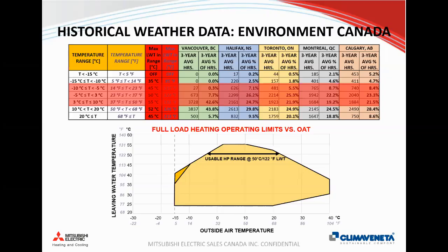So for example, if we look at a 50 degrees Celsius supply, if we look at the operating envelope, we can basically only manage that temperature as low as -5 and as high as about 22 degrees. So again, on the y-axis here, we have leaving water temperature that the air-to-water heat pump can produce according to outside air temperature. So for example, 55 degrees Celsius is the maximum supply water temperature from this type of heat pumps typically. Some of them might be able to do 60 degrees.